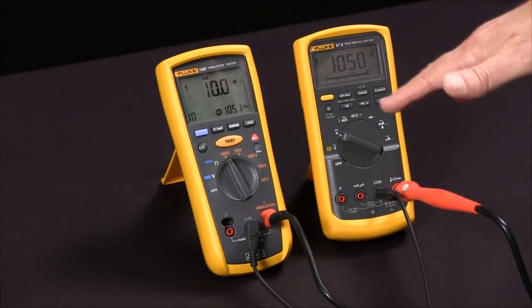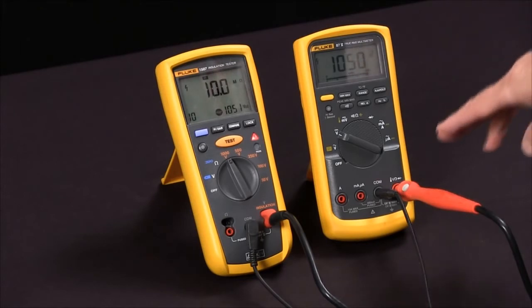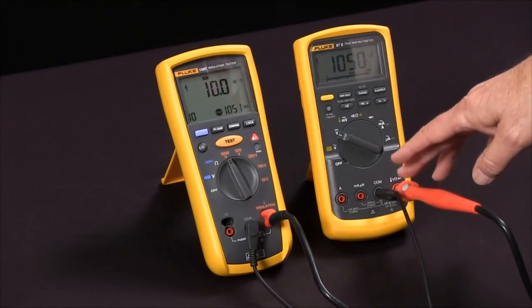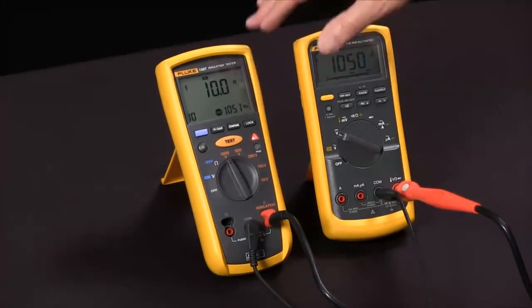Once you've completed the test, allow the meter to remain connected for a second, so it can discharge any charge that is built up on the test specimen. That's how we measured polarization index and dielectric absorption ratio with the Fluke 1587 insulation tester.